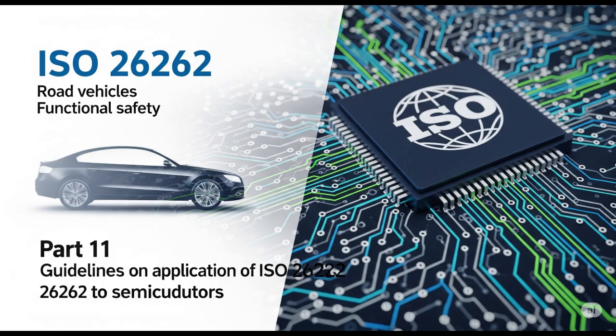Here, 2 identical CPU cores run in parallel, executing the exact same instruction stream, often synchronized clock cycle by clock cycle. A dedicated hardware comparator module continuously checks their outputs, bus signals, register writes, everything. If there's any mismatch between the 2 cores, even for a single clock cycle, an error is immediately detected and flagged. It's like having 2 identical drivers at the wheel, constantly verifying each other's every move in real time. This provides very high diagnostic coverage against random hardware faults within the CPU core itself, making it incredibly reliable for safety-critical functions like engine control or steering assistance.